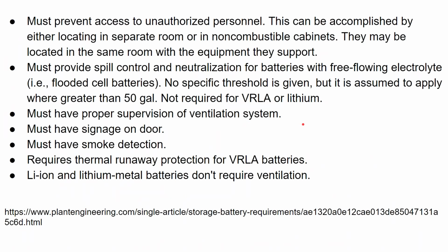Some other requirements of your battery room: you have to prevent access to unauthorized personnel. So you can't just have your batteries hanging out in your garage. They can be in a locked closet in your garage, but they can't just be in your garage. That's dangerous. You must also provide spill control for the batteries. So generally, you're going to want to put a pan underneath the batteries. It might be easiest to have the batteries up off the ground by an inch or two so that you can put a drain pan underneath.